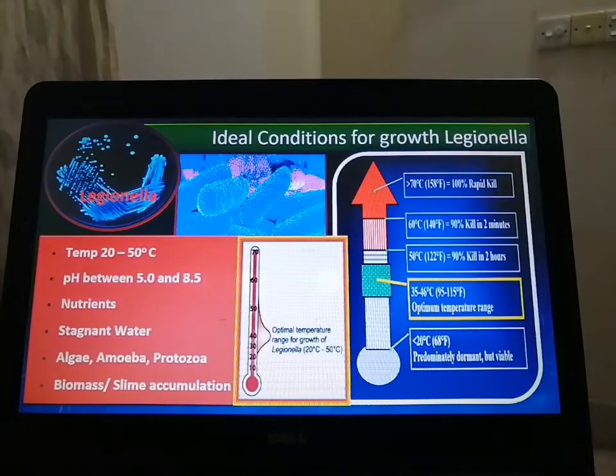It's important to understand the ideal growth conditions of Legionella: temperature required is 20 to 50 degrees Celsius, like other bacteria, and pH 5 to 8.5. If we focus on our cooling water system, all these parameters are favorable - sufficient nutrients, stagnant water. If any system has algae, amoeba, protozoa, and is contaminated by biomass or slime with microbial fouling, this kind of environment is always available in cooling towers and cooling systems.